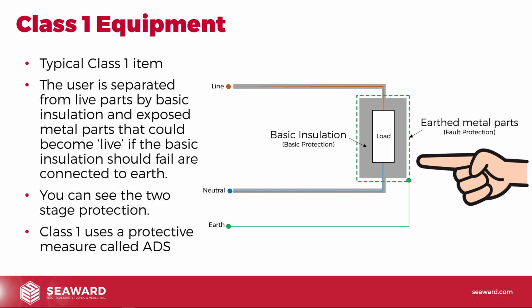Now, class 1 is a protective measure that we refer to as ADS, automatic disconnection of supply. That's the protective measure used in most electrical installations in the UK. What it means is that if there is a fault, your protective devices operate and you get that automatic disconnection of supply. The supply is switched off by the circuit breaker, the fuse blowing, or the RCD operating. In most protective measures, ADS being one of them, you will see this double layering of protection. We've got the basic insulation providing the basic protection, then we've got the earthed metalwork and the earthing, the ADS, as the fault protection. So we've got both basic and fault protection.